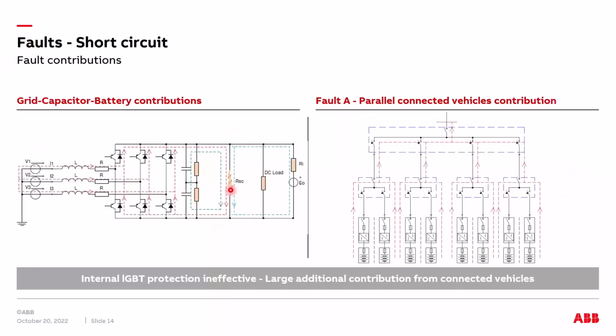So here on the left we have the summary of the three contributions coming from the AC grid, the DC capacitor, and from the local generation of the batteries during a short circuit, generally speaking, in our system. But if we have a fault in A, we have the contribution coming from the AC grid and the DC capacitor. And here, let's say the blue contribution is made by all batteries installed in parallel in that point and connected to the DC chargers. So here the contribution is, let's say, proportional to the number of batteries. The higher the number of batteries, the higher the total contribution coming from them.